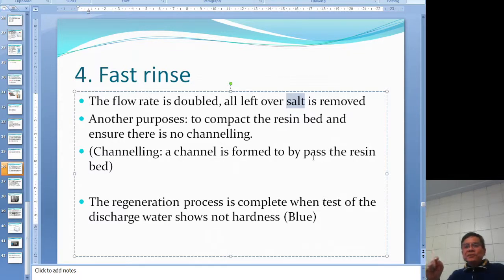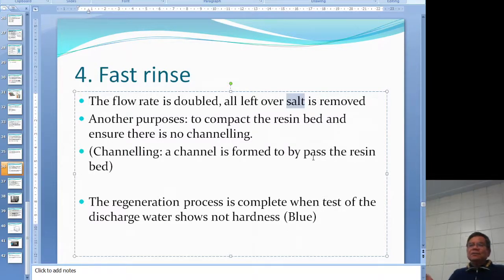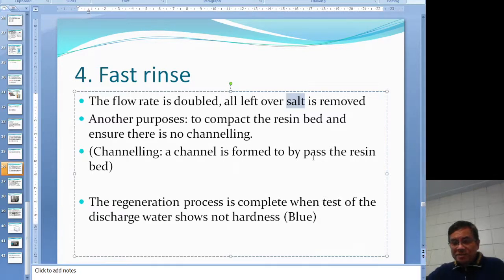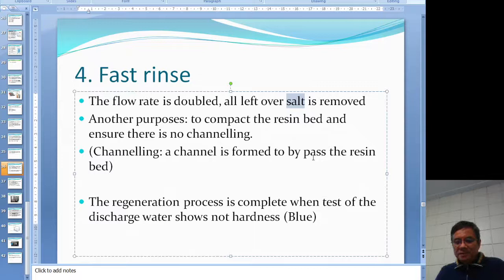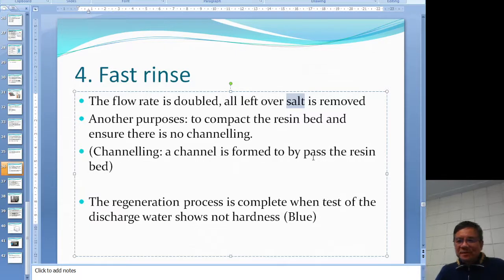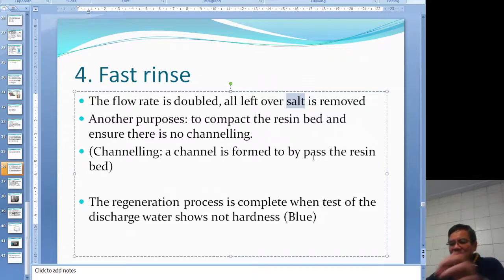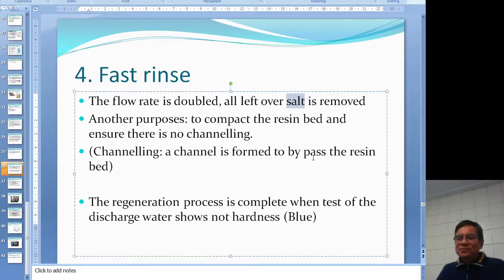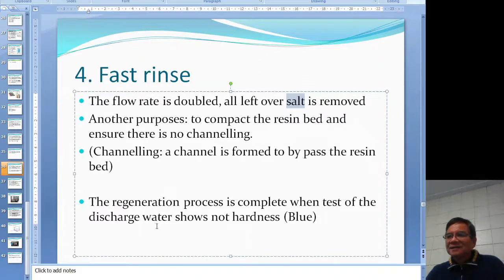After regeneration, the fast rinse takes about 5 to 10 minutes depending on your process. During the slow and fast rinse, you take a sample from the drain and test the water. If you test the water after the softener and it turns blue, that indicates low hardness, and then you are done. That is the end point of the regeneration process.